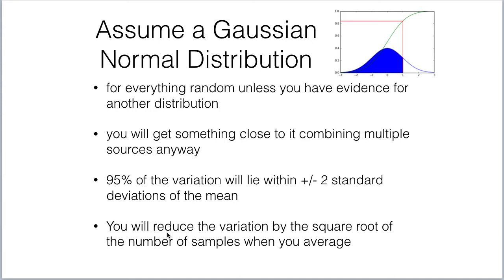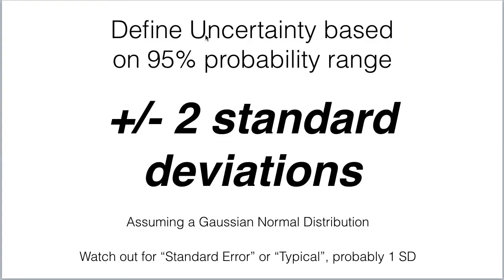If you take many samples and average them, you're going to reduce the variation in the mean by the square root of the number of samples. So if I take 100 samples, my mean will have 10 times less noise than my single samples. Always base yourself on 95% probability — plus or minus two standard deviations — and assume a Gaussian normal distribution. Watch out for people who talk about standard error or typical accuracies; they're probably just looking at one standard deviation, so you'll probably have to double those numbers.